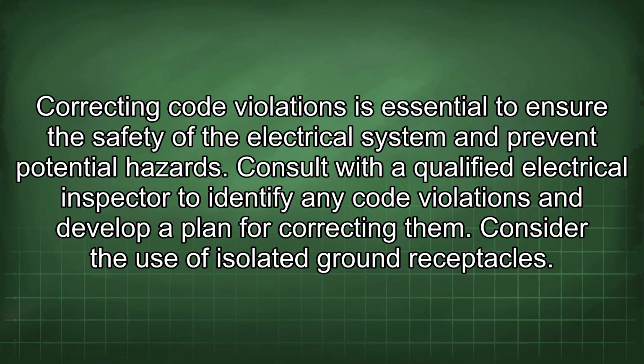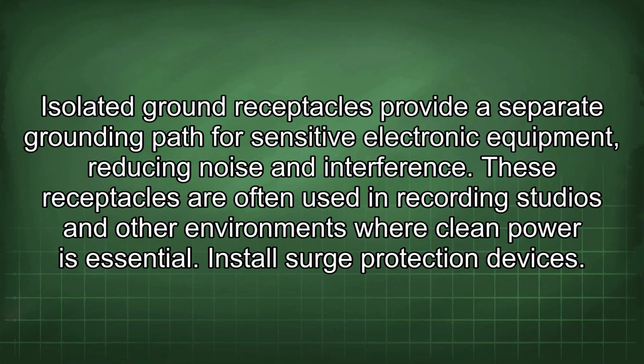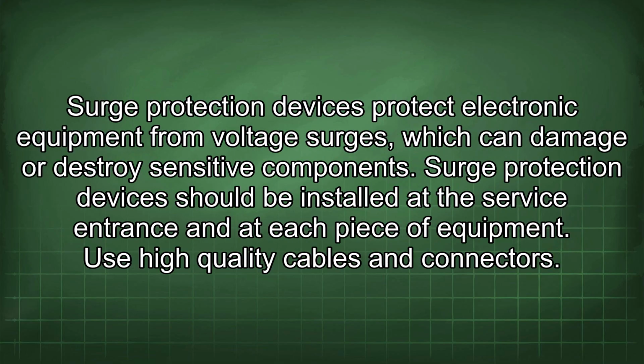Consider the use of isolated ground receptacles. Isolated ground receptacles provide a separate grounding path for sensitive electronic equipment, reducing noise and interference. These receptacles are often used in recording studios and other environments where clean power is essential. Install surge protection devices. Surge protection devices protect electronic equipment from voltage surges which can damage or destroy sensitive components. Surge protection devices should be installed at the service entrance and at each piece of equipment.